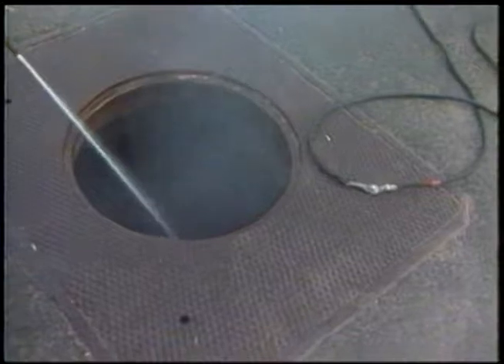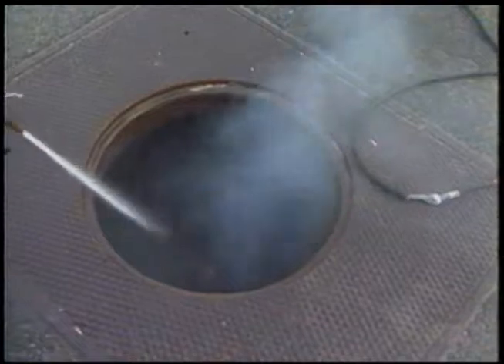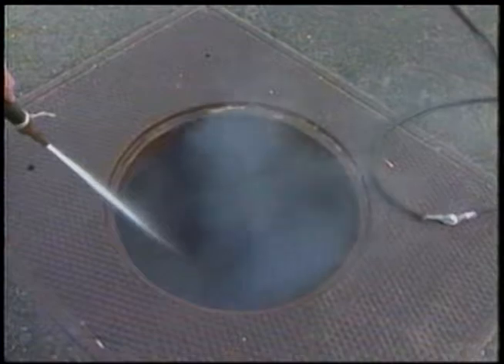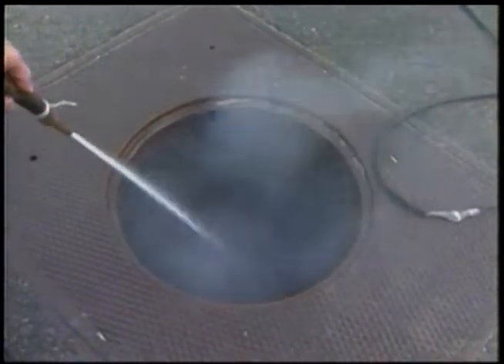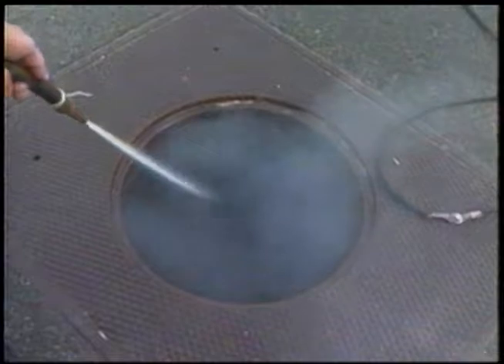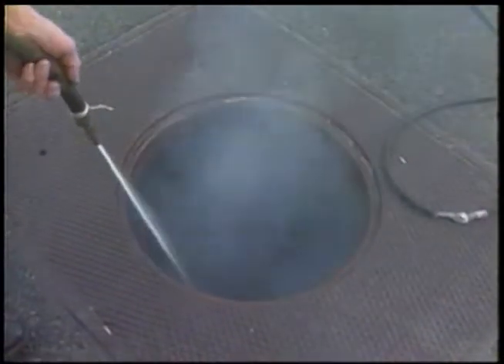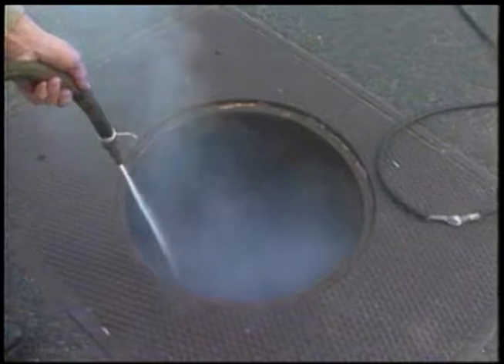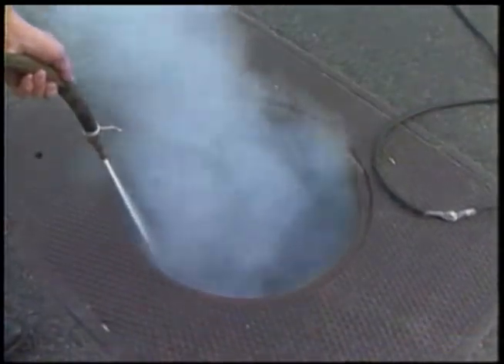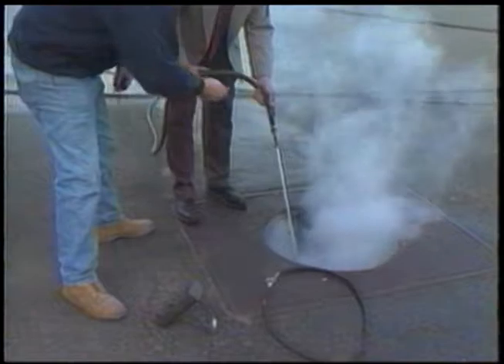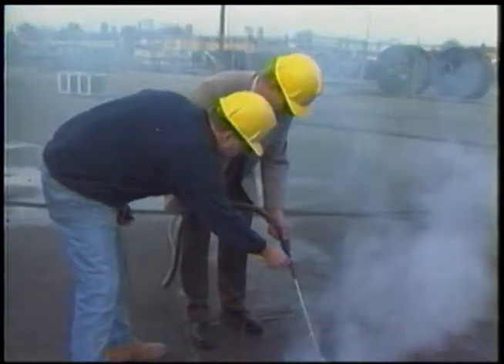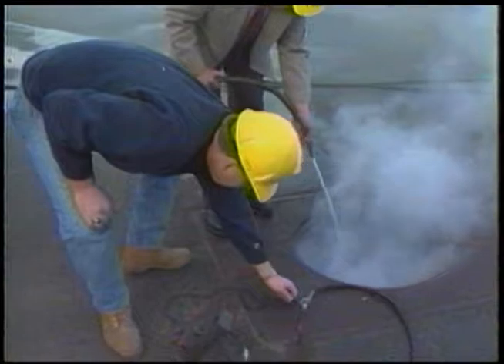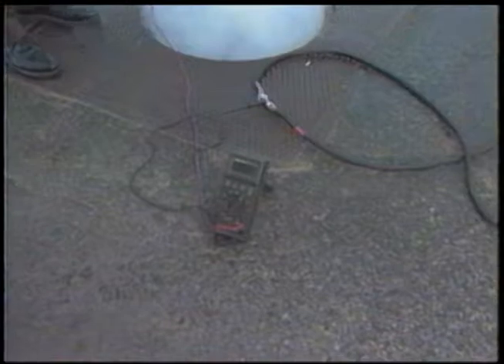Okay, now that I put the fire out with the water, the arc is still going. There's a lot of smoke right now. We're not going to see too much. Dennis, can we measure the voltage? We're going to measure the voltage. I can't see the fault. There's so much smoke. What kind of voltage are we getting, Dennis?